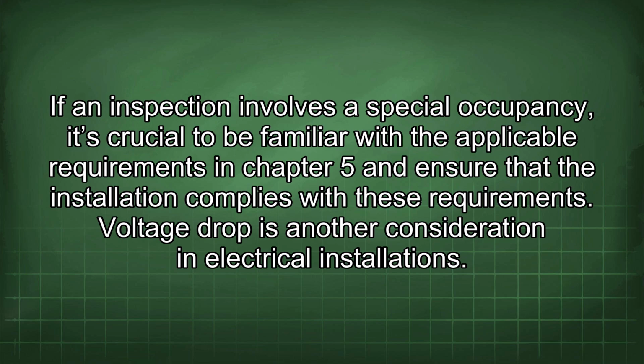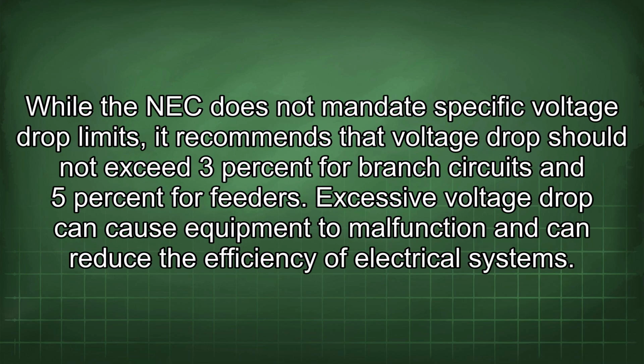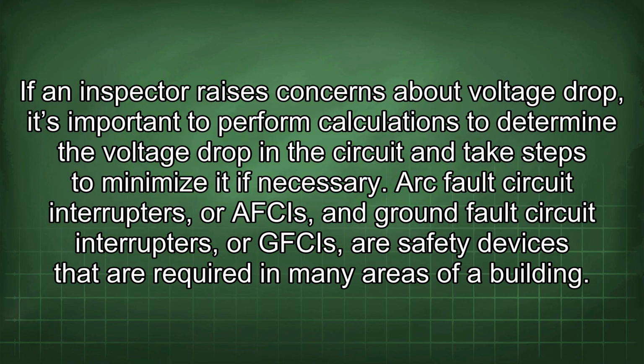Voltage drop is another consideration in electrical installations. While the NEC does not mandate specific voltage drop limits, it recommends that voltage drop should not exceed 3% for branch circuits and 5% for feeders. Excessive voltage drop can cause equipment to malfunction and can reduce the efficiency of electrical systems. If an inspector raises concerns about voltage drop, it's important to perform calculations to determine the voltage drop in the circuit and take steps to minimize it if necessary.